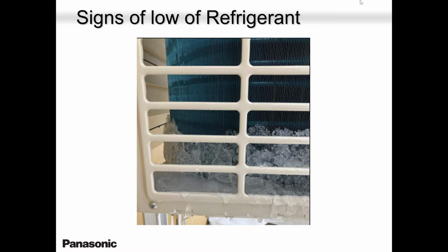Thankfully, till today, I don't know in your area, but in our area here, very cold it gets, and I have never seen our coil busted. I have never seen a Panasonic coil busted. Touch wood. So please, even though I have said that, if you are low on refrigerant, recover everything and recharge. We need that coil to completely defrost, and we need enough refrigerant to completely thaw, defrost the entire coil from top to bottom.